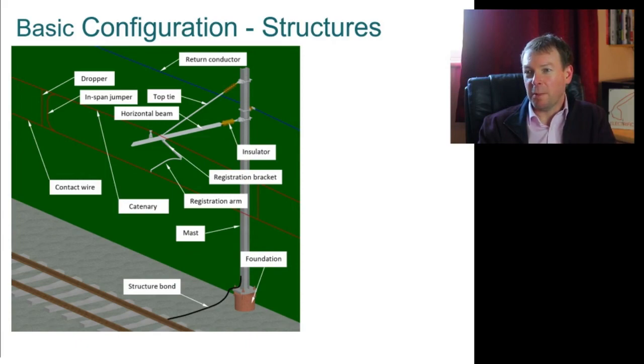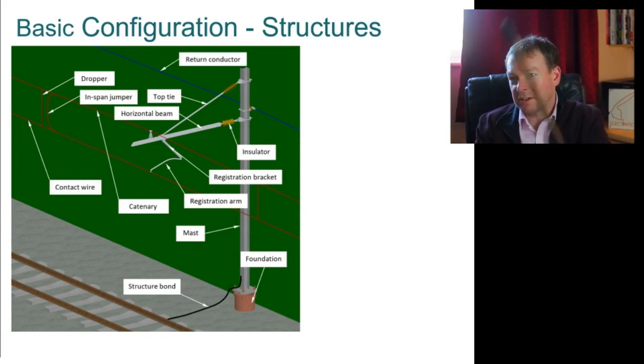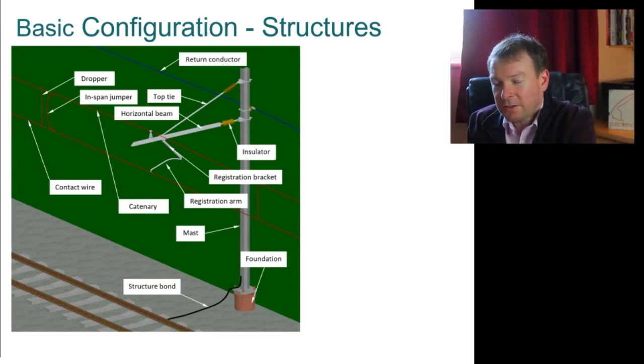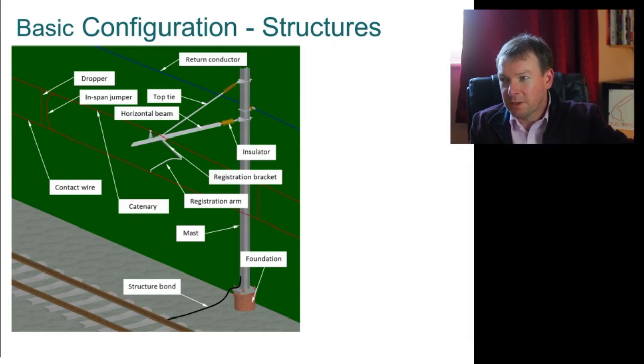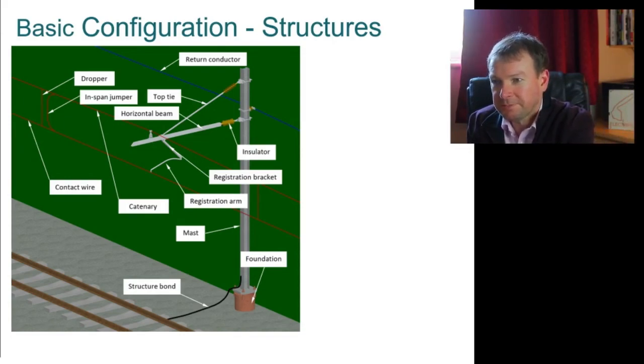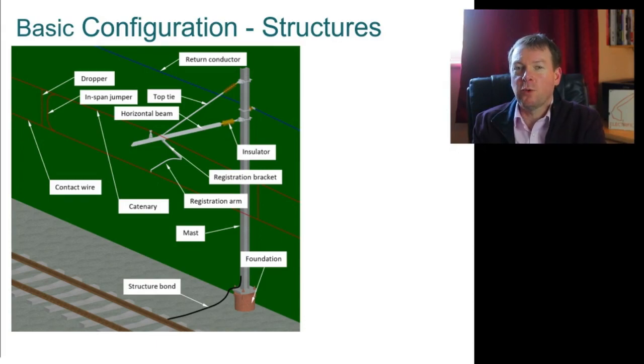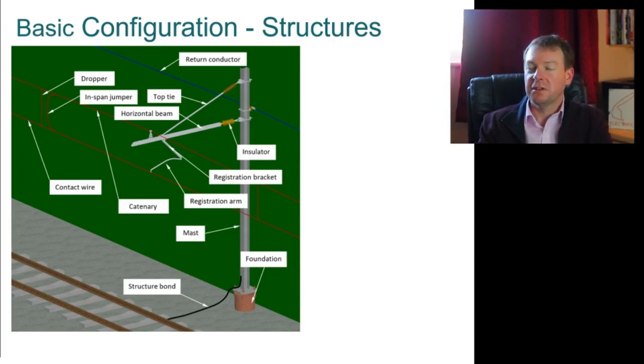Then we have the upper of the two wires, the catenary. You can see the catenary, which is the one I spoke about here. And that supports the contact wire, this one, through a series of droppers. We will then also sometimes have what we call ancillary conductors. There's different kinds depending on the feeding that we're adopting. It could be a return conductor, it could be an aerial earth wire, it could be both. It could be an auto transformer feeder, but they will typically hang directly onto the mast or on an insulator onto the mast.